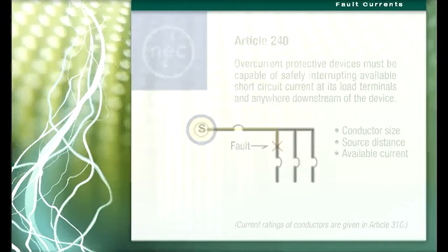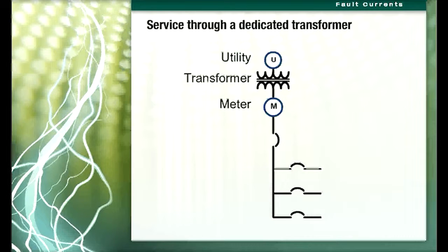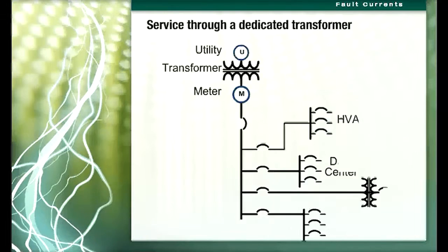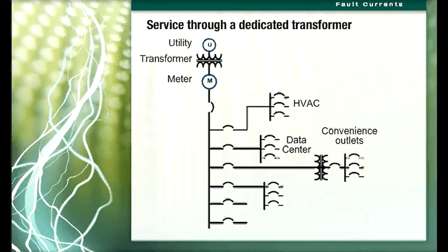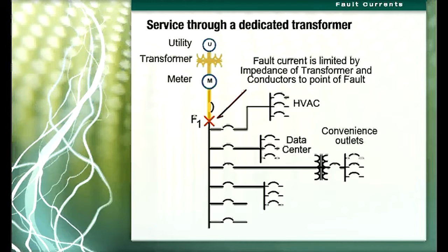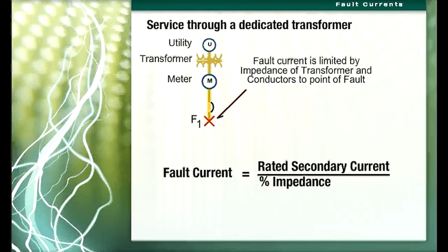Except where the service to a facility is limited by the utility infrastructure, when the service is a dedicated transformer a conservative estimate of fault current on the secondary of the transformer can be made by assuming an unlimited available KVA at the primary. In the circuit shown here, the service is through a dedicated transformer. The short circuit or fault current available at F1 will be limited by the impedance of the transformer and the conductors to the point of the fault. The fault current available at the secondary terminals of a transformer, assuming an unlimited source at the primary, can be calculated by dividing the rated secondary current by the percent impedance.